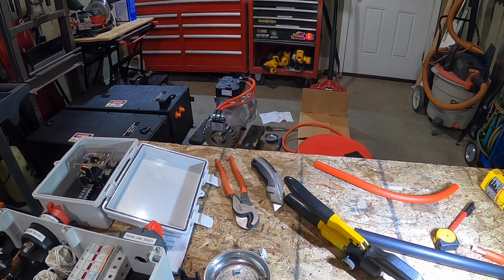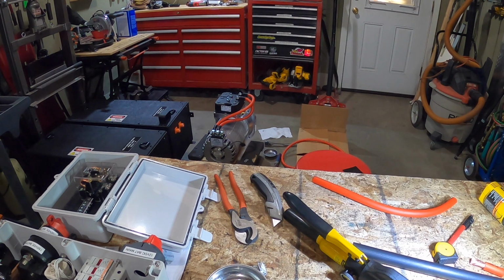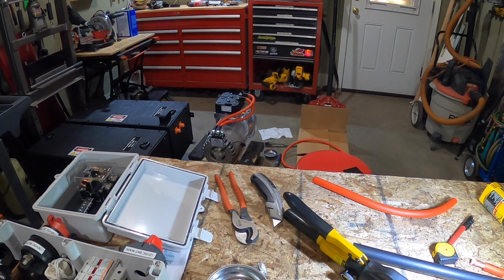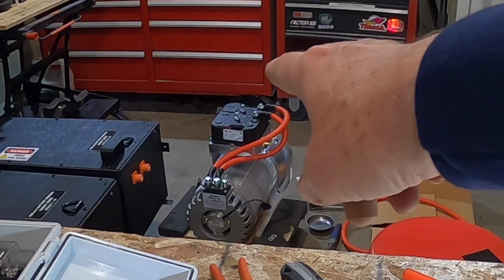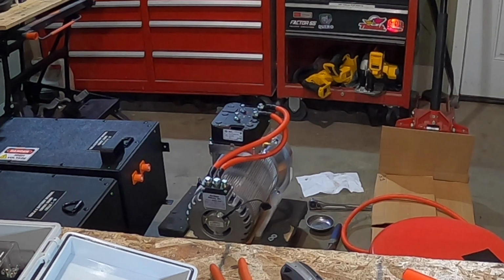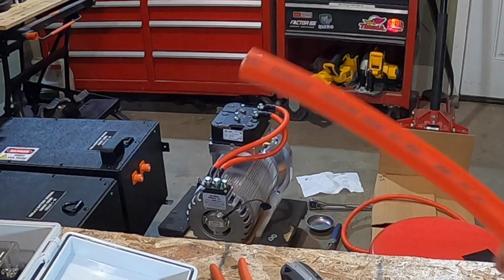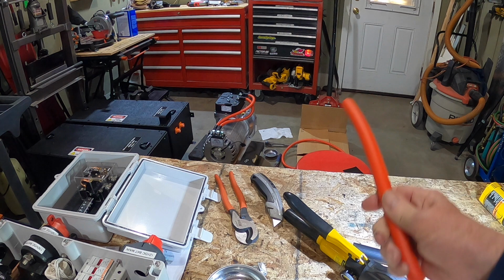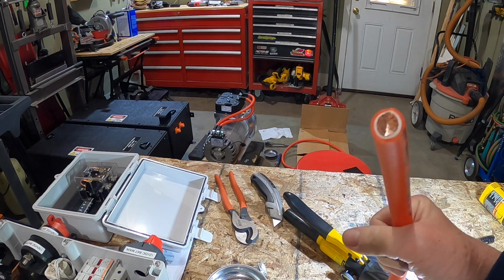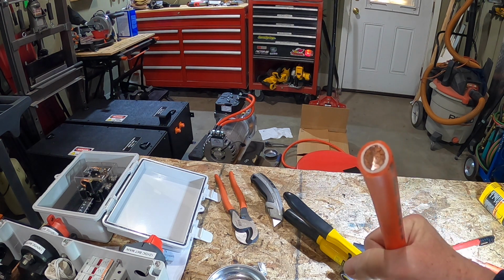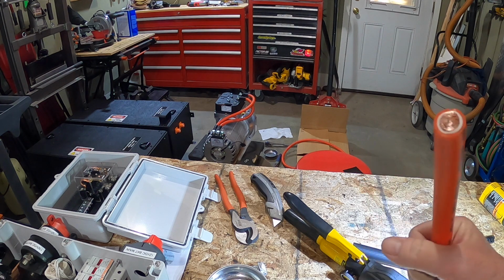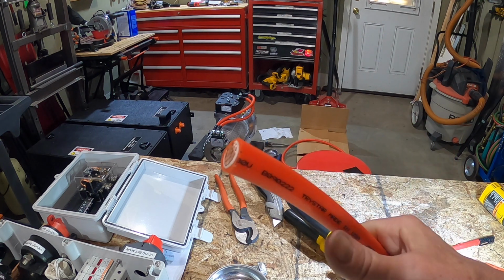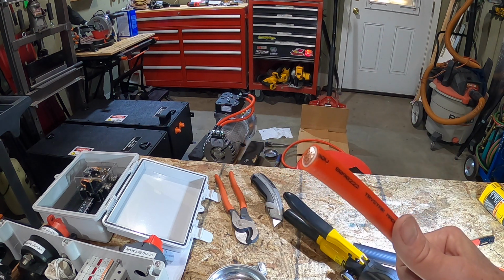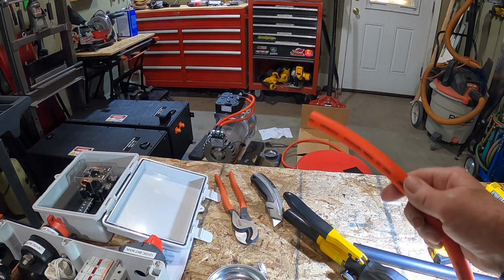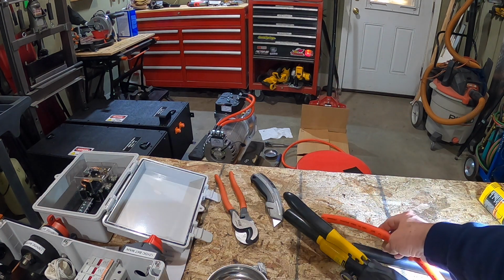I'm making up the high voltage cables for the 3-phase from the motor controller to the motor right over there. I'm using 2/0 cable, which I have about 50 feet of in a box on the floor. I have to put the lugs on each one, crimp them with a hydraulic crimper, and then shrink tube on. So let's get after this last one for the 3rd phase of the electric motor.